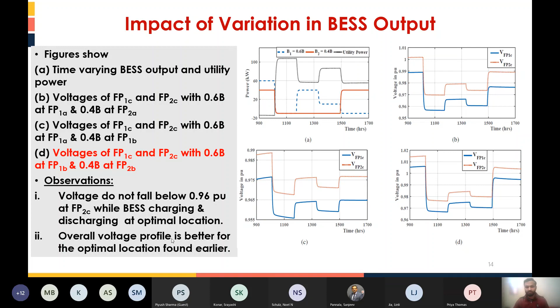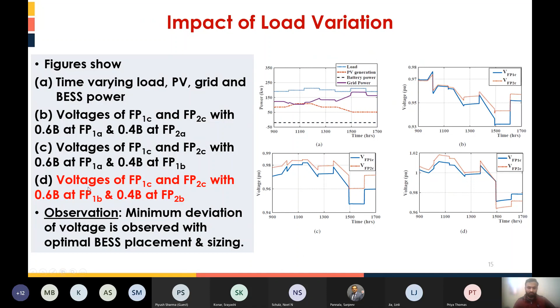Observation was that voltage does not fall below 0.96 per unit at feeder pillar 2C with the optimal placement. Overall voltage profile is better for the optimal location found earlier. The impact of load variation was also done, and here we can observe that minimum deviation of the voltage is observed with the optimal placement and sizing, which was calculated from the method. So that's it, and the conclusion: the method for optimal placement and sizing is presented for the semi-urban microgrid.